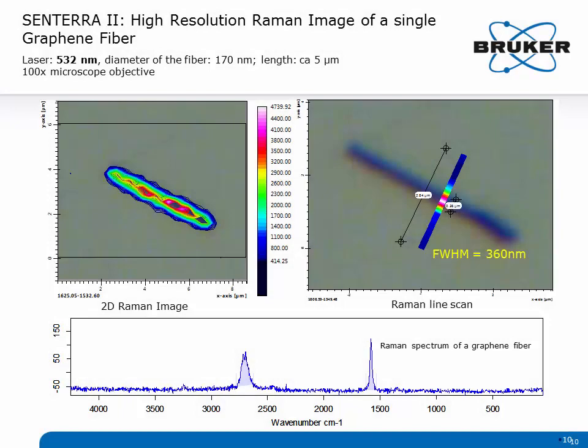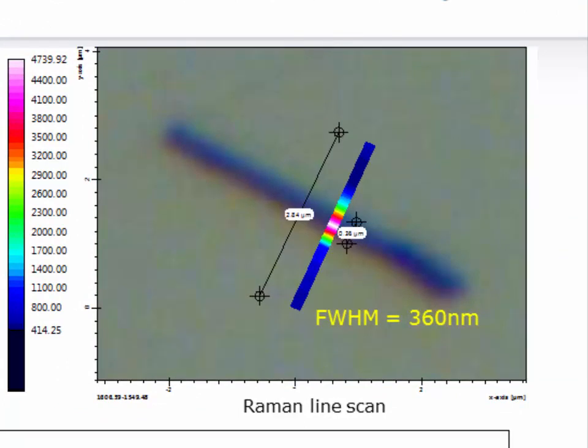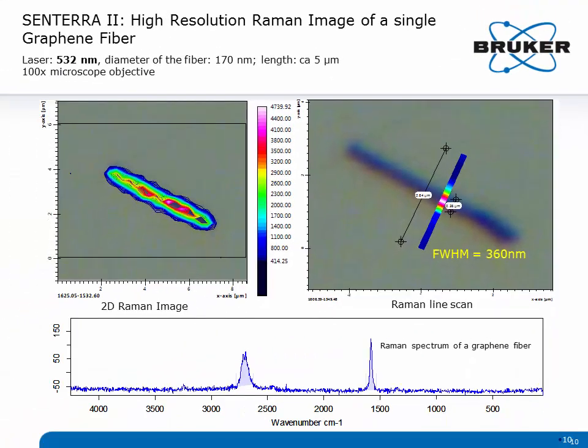For our final test, we measured a graphene fiber that measures 170 nm by 5 µm. On the left-hand side, you can see the well-defined measurement of the fiber. On the right-hand side, you can see a line map measured across the graphene fiber. The full width at half maximum is exactly 360 nm, which is also our diffraction limit. So the Senterra II Raman microscope is able to achieve the best physically possible spatial resolution.